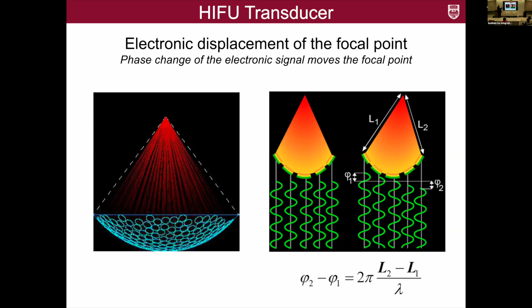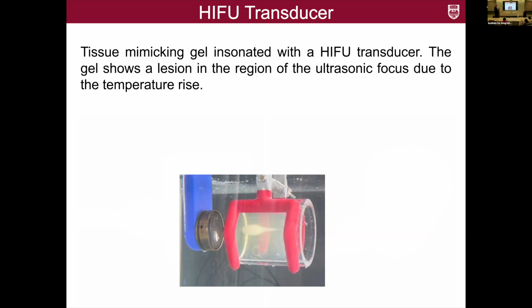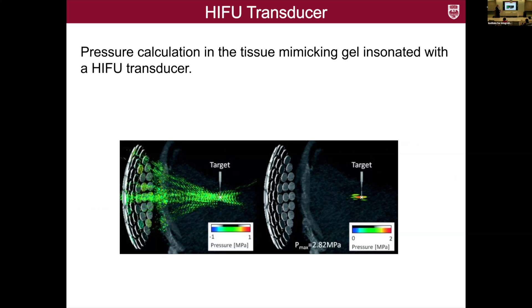This is a typical HIFU transducer. It has a power output of up to 150 watts and frequencies from 1 to 10 megahertz. The frequency is low because we want to penetrate deep into the tissue. You can see here there are also testing phantoms to see how successfully you can apply the ultrasound pulse. This is the treatment of the tissue mimicking phantom, and you can nicely see the area that can be treated. This is normally what we apply before we use the ultrasound on a patient. So we can do a pressure calculation in the tissue mimicking gel and calculate how high the pressure was at a certain location by looking at the coagulation effects that we see here.